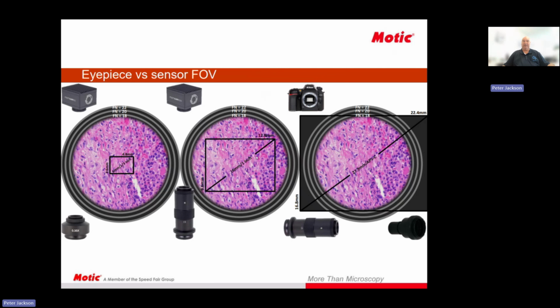Another thing to be aware of is that I see a lot of customers who expect, when you focus the microscope on a slide, that the camera is then focused, but you have to be aware that the cameras are not auto-focusing. So if you focus the microscope and then look at the actual image on your PC of what the camera is seeing, it's not always the same as what you see through the objectives or through the eyepiece. So typically you either focus manually using the microscope, or you focus specifically on the image on your computer, focusing what the camera is seeing. The two are not always exactly the same.